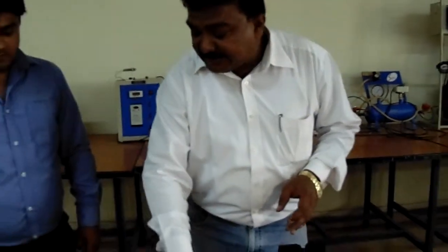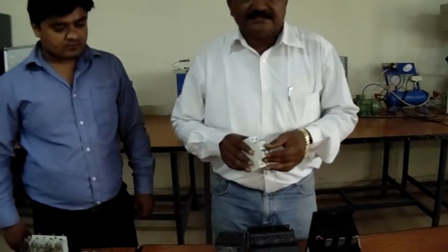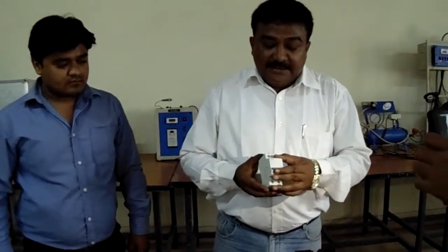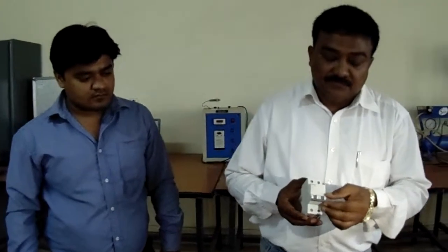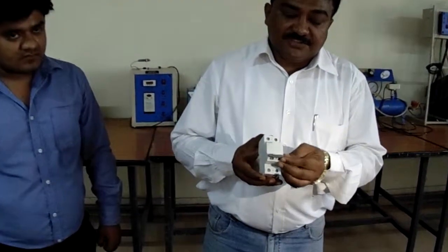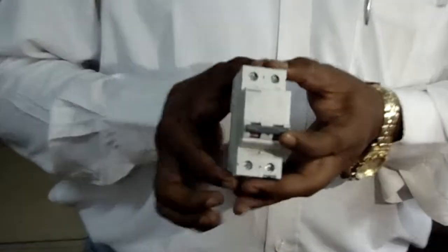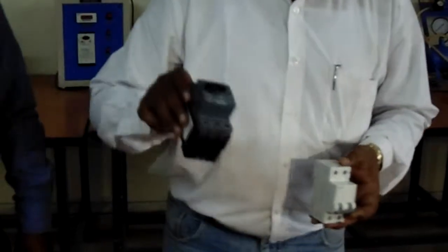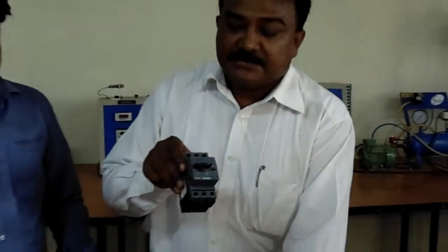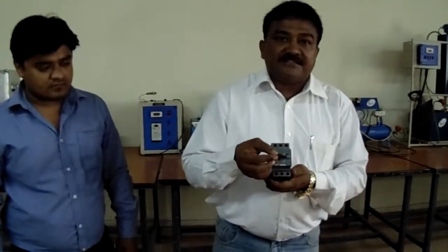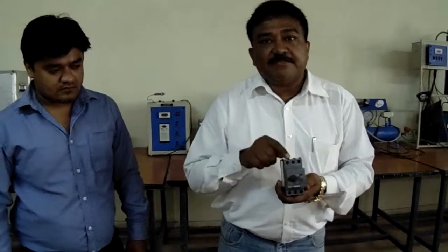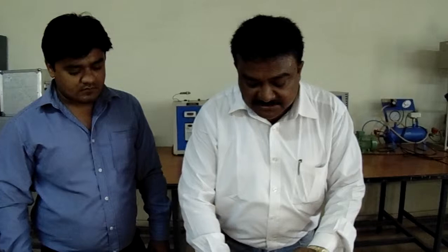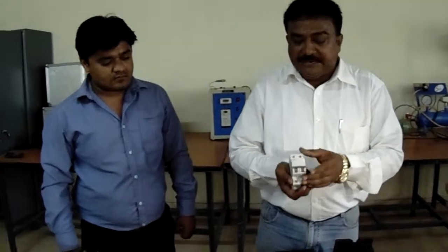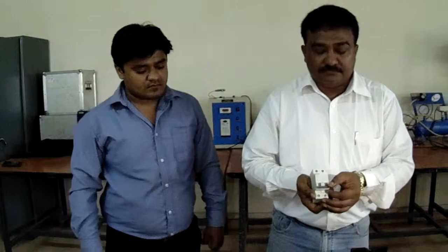Now the very important thing to be noted here is that in all the circuit breakers, in the event of any trip, the lever of the switch will be at the center of the circuit breaker. Whether it is a miniature circuit breaker, a molded case circuit breaker or a motor protection circuit breaker, in the event of any fault, when the circuit breaker trips, the switch will be in the center, which will let you know that the circuit breaker is tripped. Otherwise, in the on position, it will be at the top, and in the off position, it will be at the bottom. That's all.